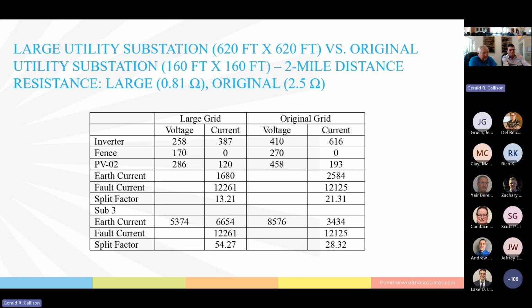And so what does that do? Well, if you remember, these numbers are basically the same as we saw earlier, but by making the utility substation larger, we have changed the voltages at the inverter and the fence and at the collector station. And the split factor changes pretty dramatically. It's almost double the split factor. So what does that do? That increases the fault current at the substation, and the voltage actually goes down because this is the current times the lower resistance value.